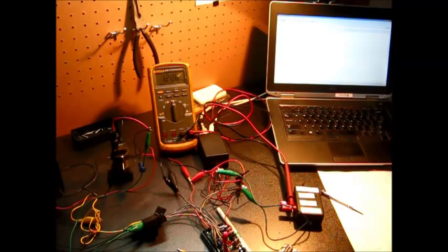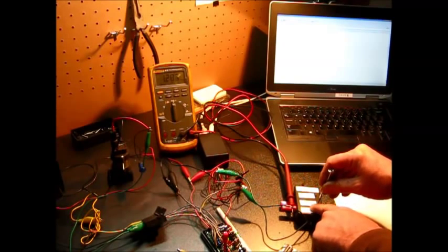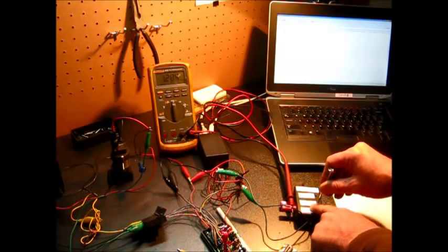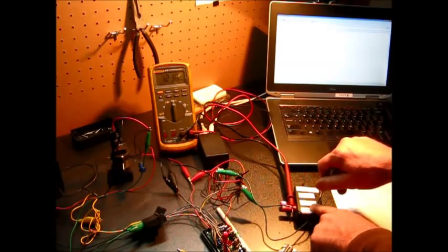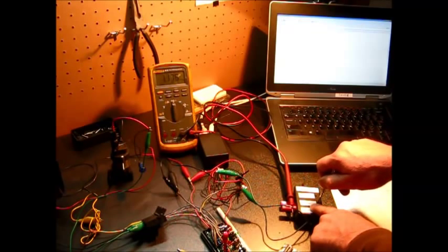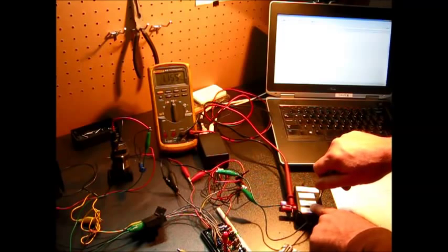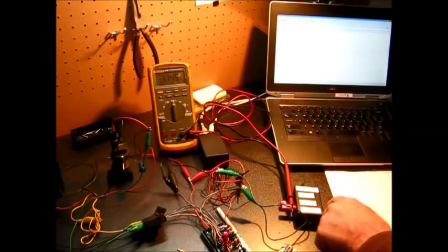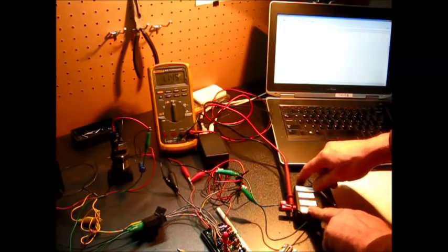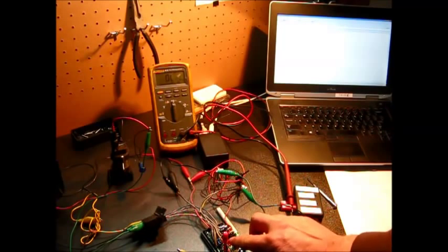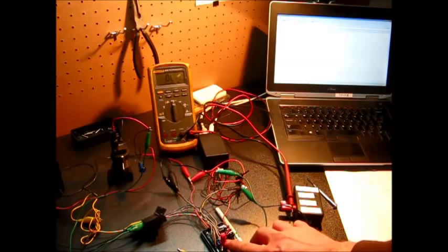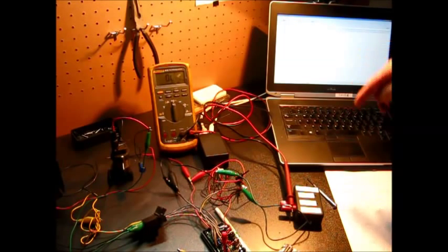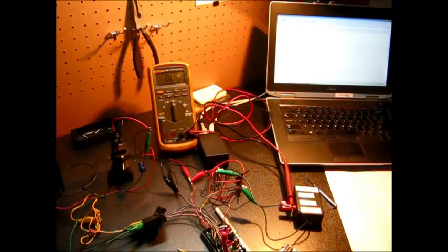We'll press this button for five seconds or so. And now it remembered that 16,639. Move on to the next one. Next set point should be 1149 ohms. We'll try to dial that in. All right, 1149 ohms. Put the same resistance on to the controller. We'll change it to set point two. Press this button for five seconds to memorize set point two. All right, now set point two is saved in the memory. And I'll go on through until all eight set points are programmed. And then come back and we will test it, function test it.